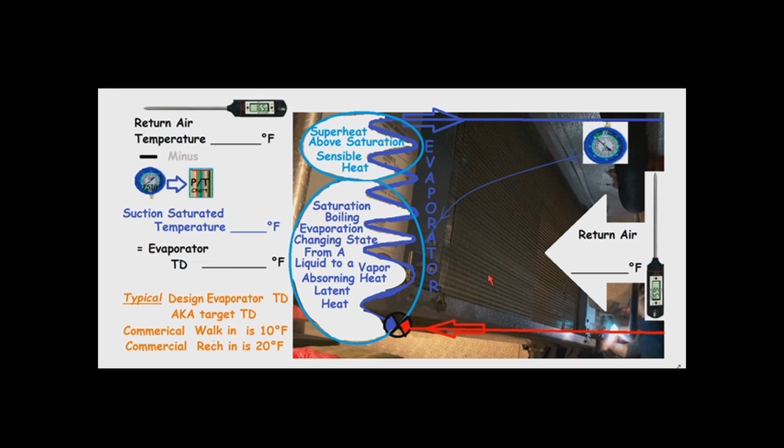air temperature. In a walk-in cooler, it's a lot more constant because your airflow is the same. Walk-in coolers don't have a varying amount of airflow. They just move a steady amount of air. They also don't do a lot for dehumidification, so it's mainly sensible cooling, which is a lot easier to work with.